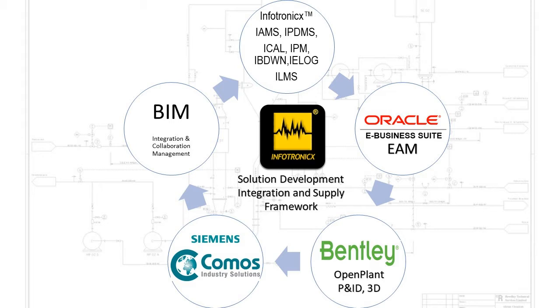Whether the project P&IDs are created with the intelligence feature or by conventional CAD methods, these lists and/or reports will no doubt be created. The fallout of the traditional system with conventional P&IDs is that these lists are created manually by taking information off of the P&ID drawing and entering that information into a spreadsheet. This process creates a situation where data exists, by necessity, in two different locations. Invariably, things change. The responsibility of managing two sets of hopefully identical data becomes enormous.